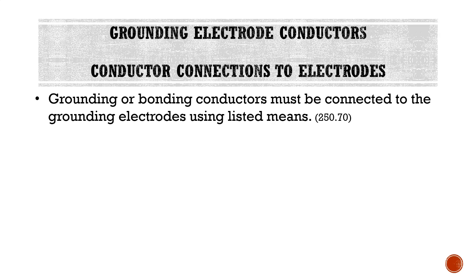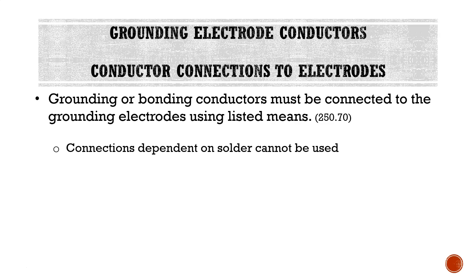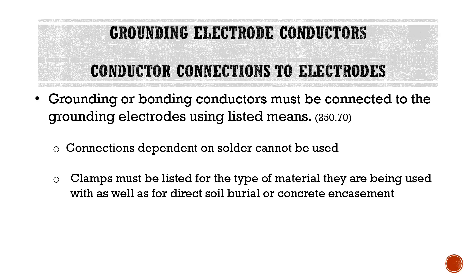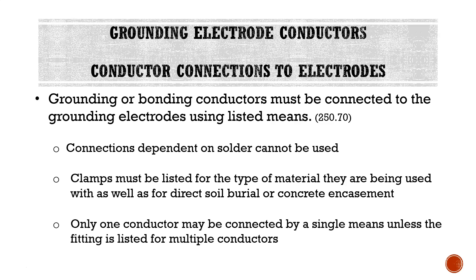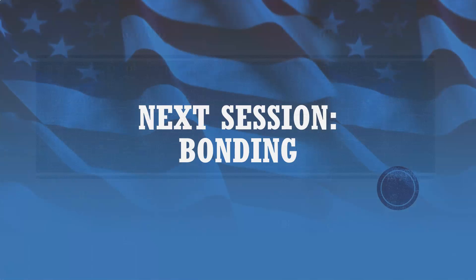Looking at our connections to the electrodes themselves: grounding or bonding conductors must be connected to the grounding electrodes using listed means. Connections dependent on solder cannot be used. Clamps must be listed for the type of material they're being used with, as well as for direct soil burial or concrete encasement, as applicable. Only one conductor may be connected by a single means unless the fitting is listed for multiple conductors. Essentially, if we're connecting a grounding electrode conductor to a grounding electrode, we have to use a connection means listed for that type of connection. That wraps up this lecture — in our next session, we're going to be taking a look at bonding.